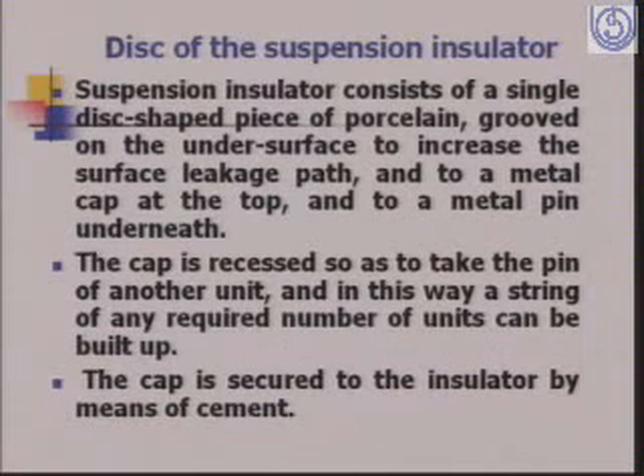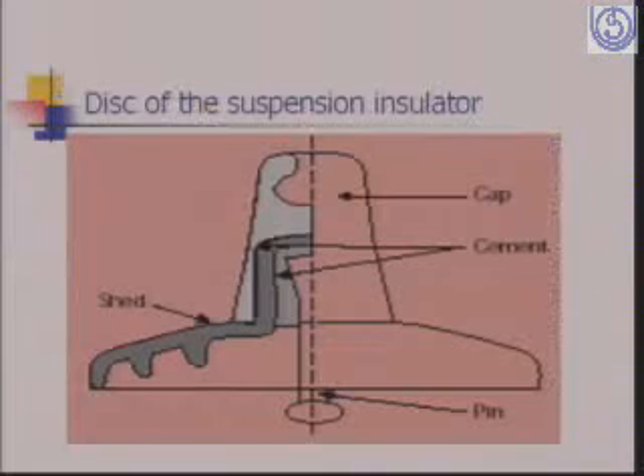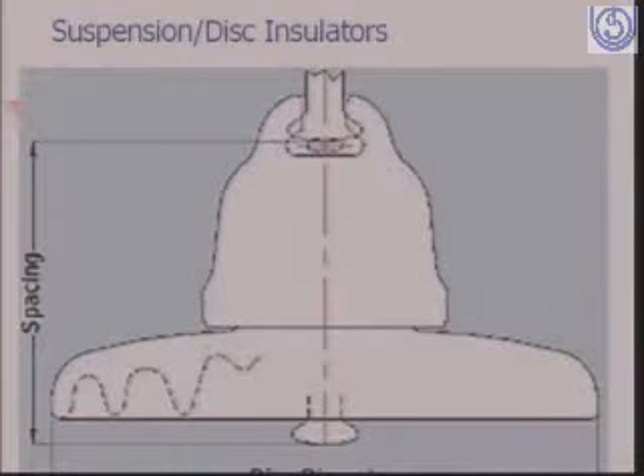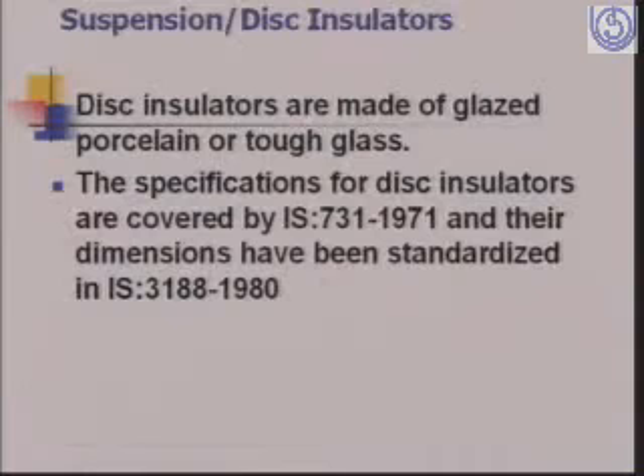The disc of the suspension insulator consists of a single disc-shaped piece of porcelain grooved on the undersurface to increase the surface leakage path, and a metal cap at the top and a metal pin underneath. We can see this. This is a disc of the suspension insulator. Again, this is the disc of a suspension insulator. The disc insulators are made of glazed porcelain or tough glass. The specifications for disc insulators are covered in IS 731, and their dimensions have been standardized in IS 3188.